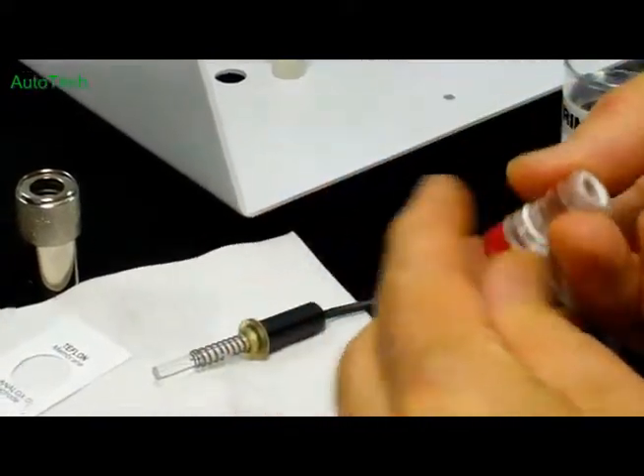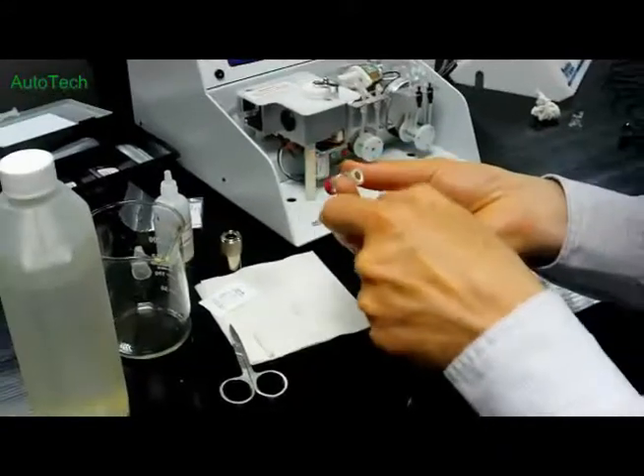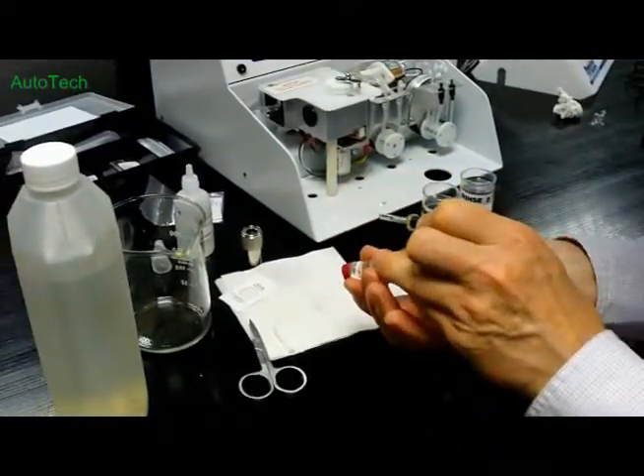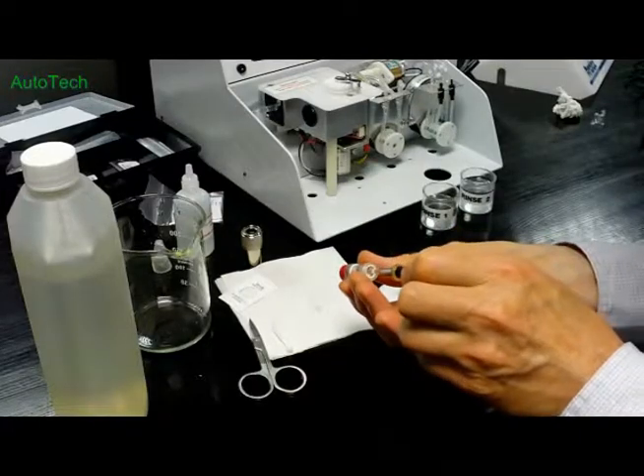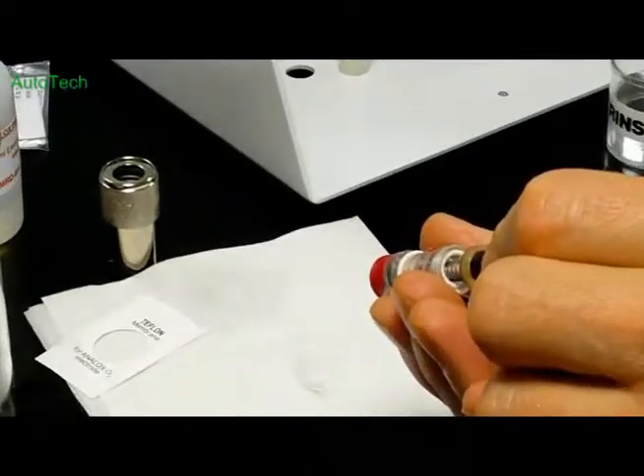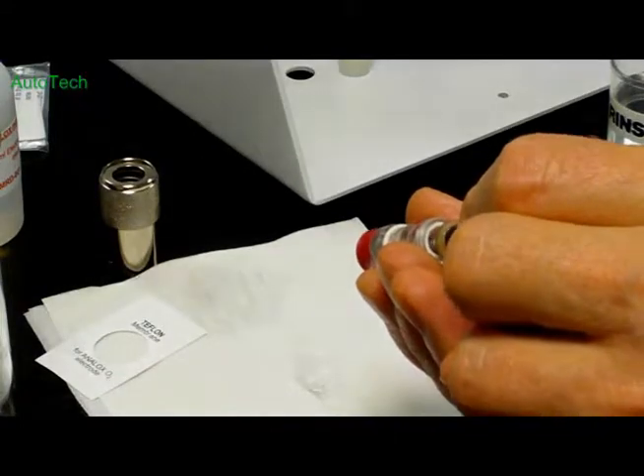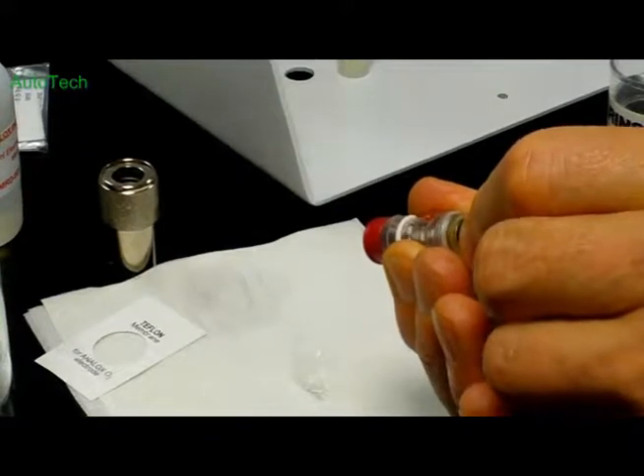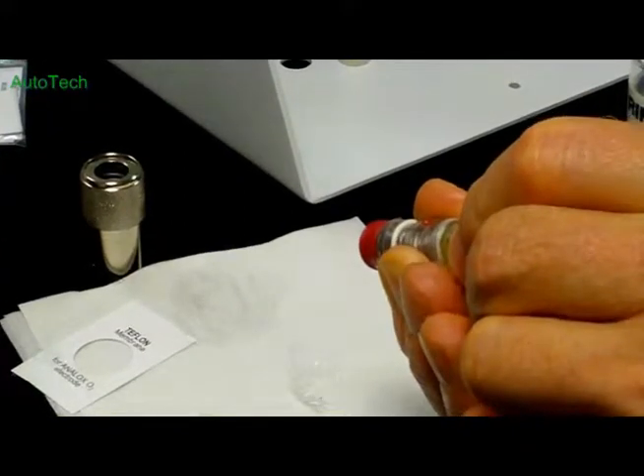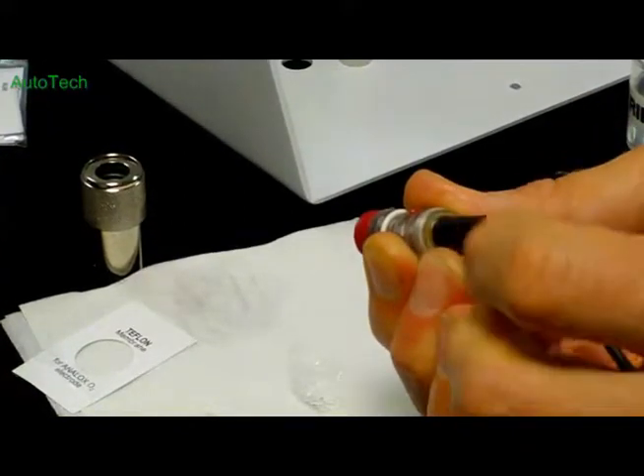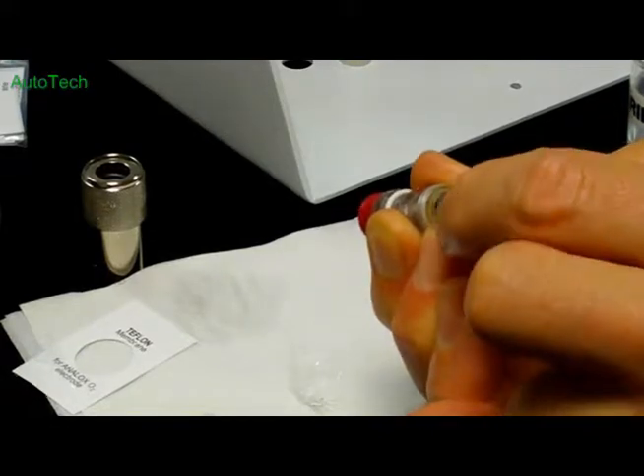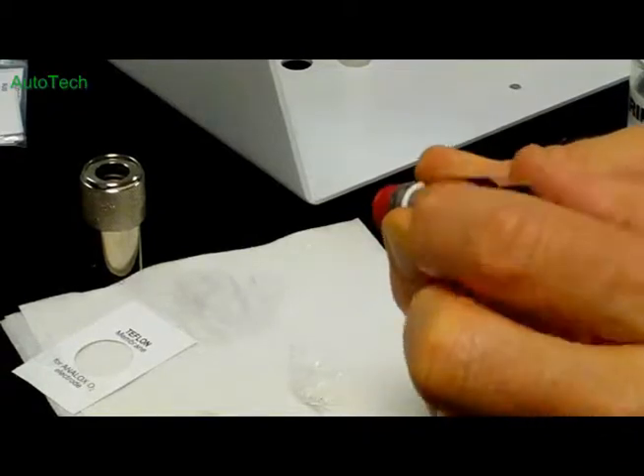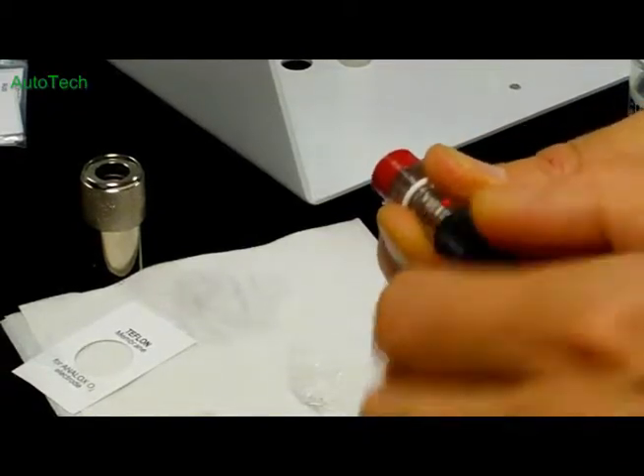So now we're going to insert the electrode into the jacket with the red dot uppermost. So gently insert the jacket. It'll displace the electrolyte. That's perfectly okay. And right at the end, you will see a little bit of electrolyte come out. Maintaining a bit of forward pressure on the cable. So we'll gently drop the black back nut until it's firmly tight.